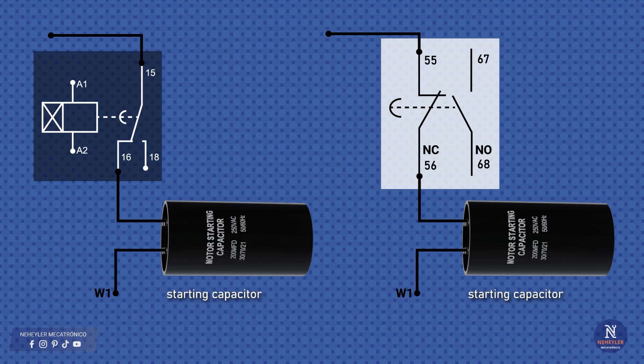On screen we see two ways to represent the start capacitor connection. In both cases the capacitor is connected through a normally closed contact. The function is the same, when starting the motor the contact is closed and the capacitor enters service, after a few seconds the contact opens and the start capacitor is disconnected automatically.